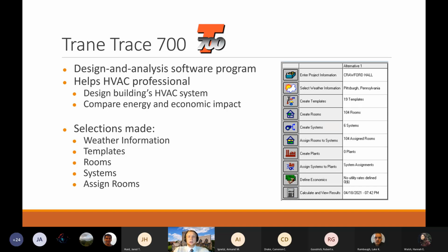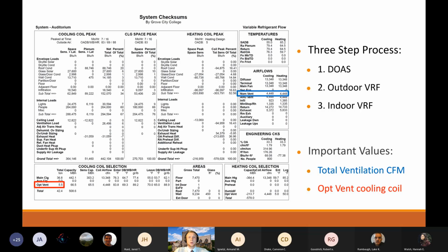So this is what the interface looks like, and it's also an overview of the different selections we made. So we selected the appropriate climate based on our location. We made numerous different templates based on the wall and roof construction, the location of the rooms within the building, and the desired heating and cooling temperatures. And then we used these templates to create individual rooms, which we divided up into different spaces of the building. Then we created 6 cooling systems and assigned the rooms to each one of these systems. After we made these inputs and ran our calculations, we had to run Trace, and it provided us with numerous different results sheets. For our project, the systems checksum sheets and the zones checksum sheets were particularly helpful in determining the correct sizing for the system and the equipment.